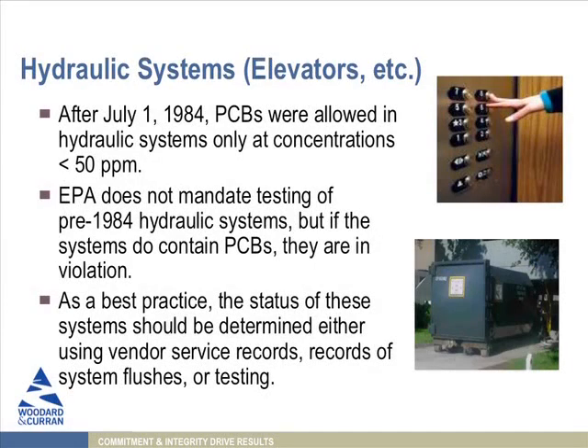If you have a leak or have to deal with hydraulic fluid and you don't know anything more about it, you have to presume it has above 50 parts per million and treat it as PCB waste accordingly. As good management practice, you may want to have it tested, especially if you think you'll need work done on it at some point, so you know what you're dealing with. What you don't want is to have a leak or spill as an emergency and, in the absence of knowing anything more, have to presume it's PCB waste.